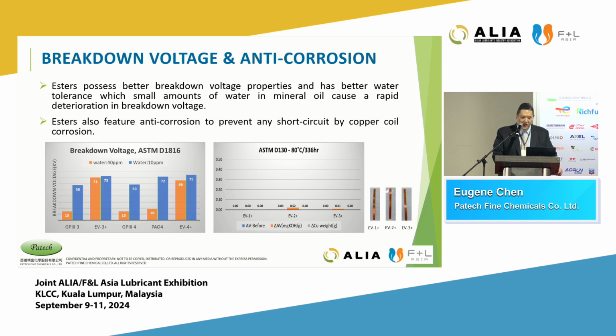As far as the copper corrosion test, on the bottom right, we did the standard ASTM D130, 80 degrees C for 336 hours. Looking at three of our products, they all pass the copper corrosion test with a very good result, with no corrosion shown on the copper strips.